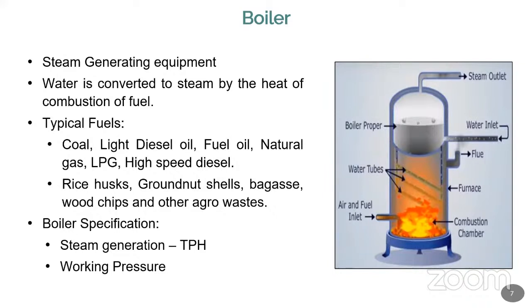Okay. So it is a pressure vessel which produces steam, and water is converted into steam with the help of heating by the fuel. Right. The fuel may be coal, LDO (light diesel oil), furnace oil, natural gas, LPG, or high-speed diesel. The second category is rice husk, coconut shell, bagasse, wood chips, and agro waste like any other agro waste. Even rice husk is agro waste. So when you go to any rice manufacturing industry, especially modern rice mills, they use rice husk as the main fuel for running the boiler. Almost 100% of the rice husk is used by the same industry as an input for the boiler, so they do not need to buy additional or alternate fuel for the boiler.